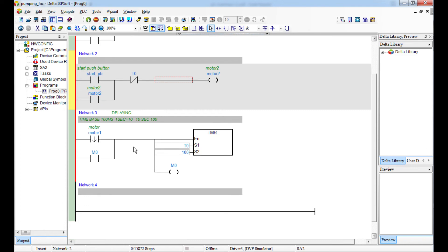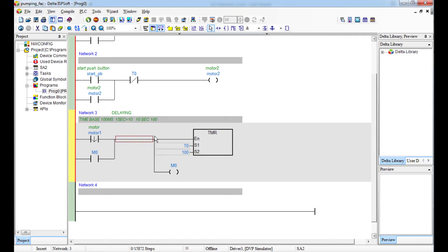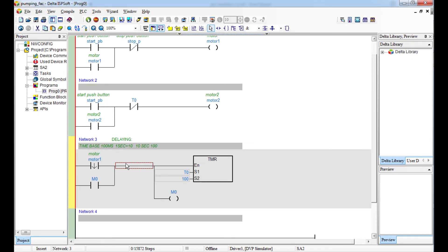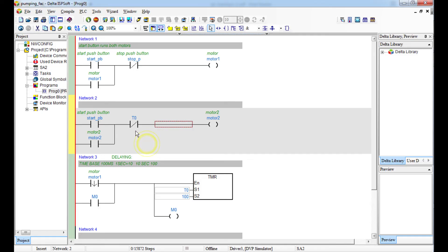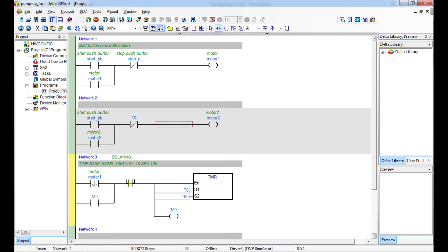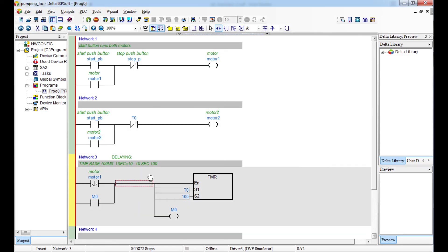After the timer fires, the M0 coil must also reset. If it doesn't reset, the next time you try to start the system the timer contact will still be energized, Motor 2's circuit will remain open, and you'll only be able to run Motor 1 but not Motor 2. So I need to deactivate M0 as well.